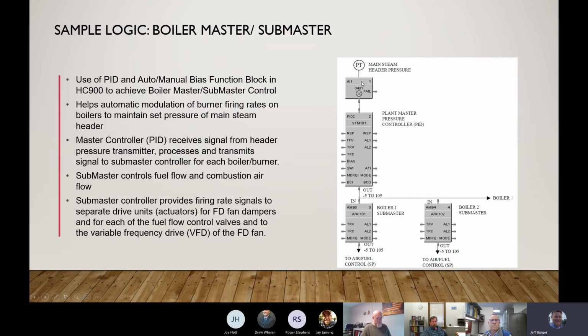So you have an analog input coming in, which is your main steam header pressure. And the way that I know that this function block is an analog input is over on the left-hand side, you see it says AI. That stands for analog input. So at a very quick glance, I can see that that's an analog input. If you move down through this function block, you'll see 0401. And as I configure my I/O on the rack, this tells me where this analog input is hooked up or wired up to. So on this one, it says 04 is rack number 4, and it's the, I'm sorry, this is the analog input card number 4 and the channel 1 on that analog input card number 4. So if I had a 4-slot chassis, that would be I/O slot number 4 and then channel 1 on that card. As I program these function blocks, you'll also see on the far right-hand side a number.